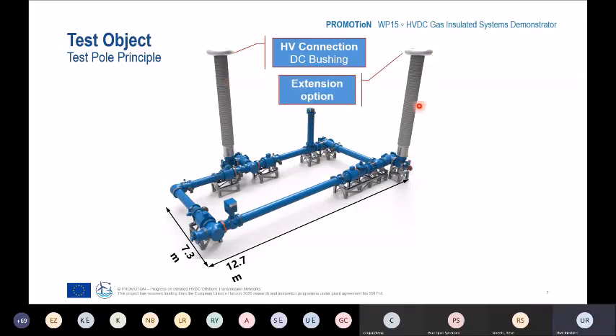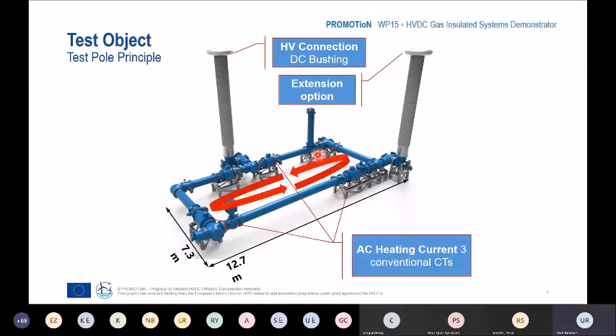Another bushing for tests across the disconnector switches. And we have formed a ring to create a current inside this loop here. The current is an AC current, so we have used 3 conventional AC current transformers to create a current of 4000 amps AC. That is a requirement, especially for DC testing, to have a full load during testing, because the temperature, especially the temperature difference between the inner conductor and the outer conductor, is of main importance for the field distribution.